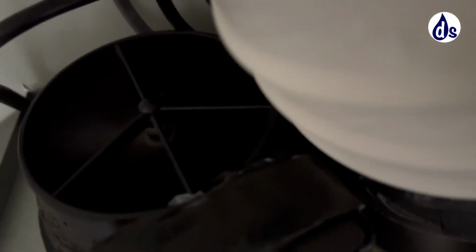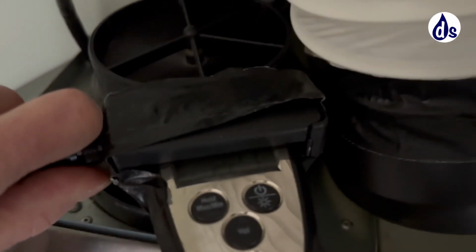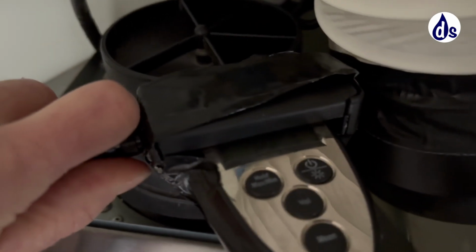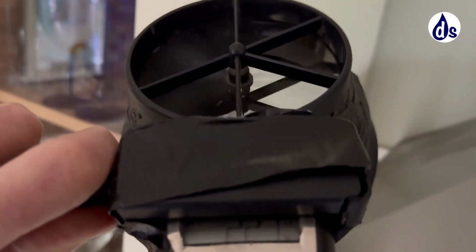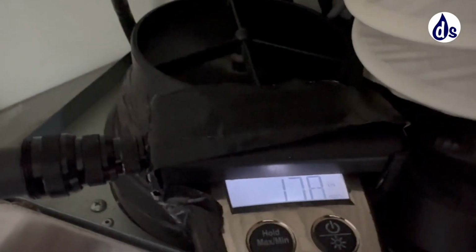Taking those out, see how that goes. So the actual fan is producing 18, 19, but I've got a maximum of 22. So it's not running very fast. It must be, I guess, a bit old. In order to achieve a 30 outflow, which is what you need, you really have to have at least 40 coming out of here, and it's 80.